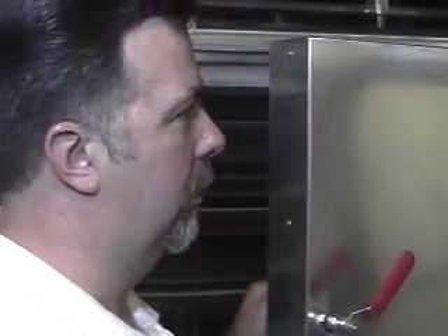Well, that sucks. Can't we just shut them down? That's the fun part. Then you get all the calls. That's right. I'm not sure what the protocol is if you have to shut down the lab exhaust. It calls for the lab exhaust fans to run all the time. Yeah, it's probably put all the exhaust hoods in alarm. Yeah, and you start venting stuff you don't want to. It's like the other building, they don't want to ever shut off.